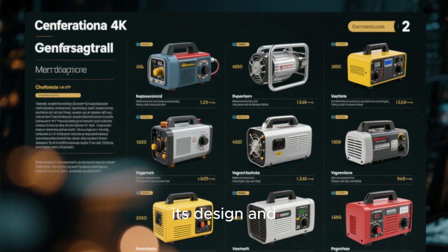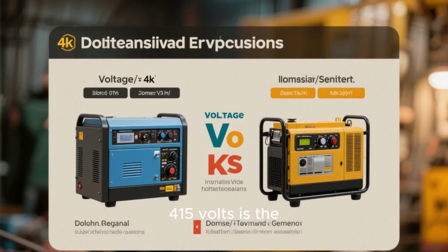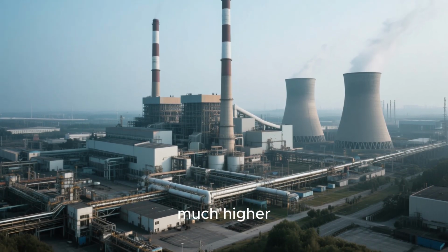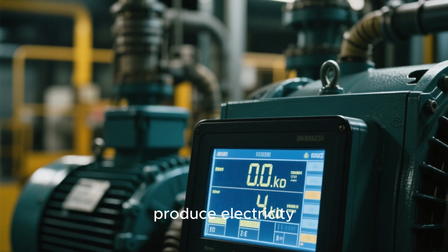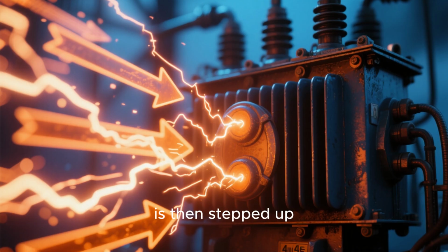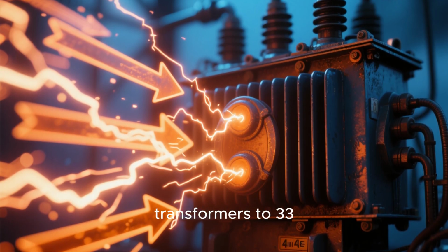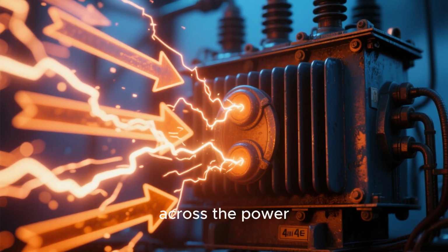Let's also briefly touch upon generator voltage ranges. The voltage a generator produces depends on its design and intended application. As we said, 230 volts is common for single-phase domestic use, and 415 volts is the standard for three-phase industrial use. But in large-scale power generation, the voltages are much higher. Generators in power plants often produce electricity at 6.6 kilovolts or 11 kilovolts. This high voltage is then stepped up even further by transformers to 33 kilovolts or more for efficient transmission over long distances across the power grid.